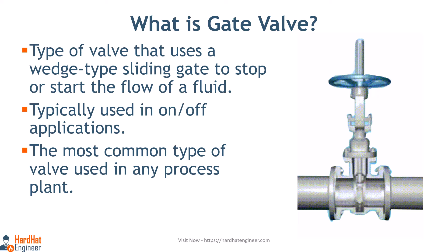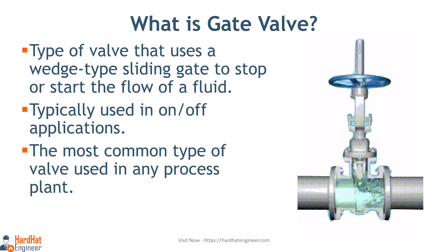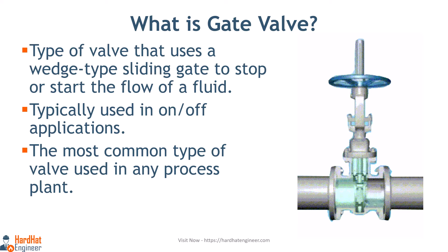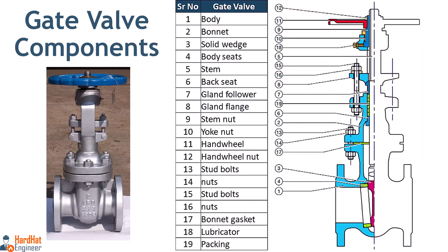It should not be used for regulation or throttling of flow by a partially open gate, because accurate control is not possible and the high velocity of flow in a partially open gate valve may cause erosion of the disc and seating surfaces, and also creates vibration and noise.